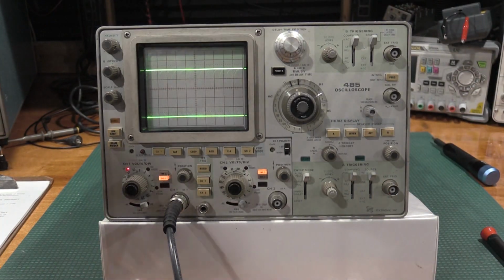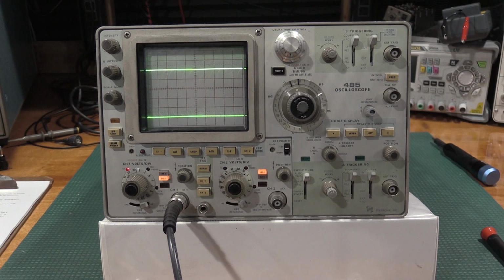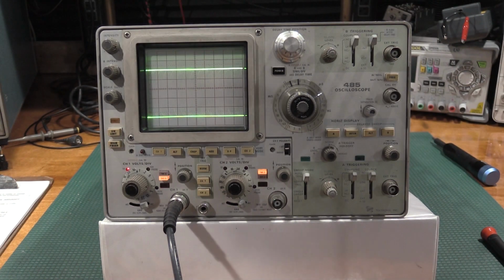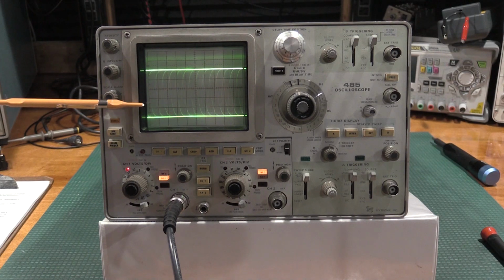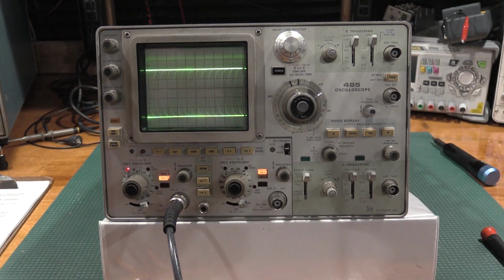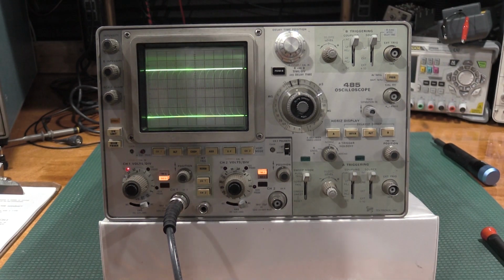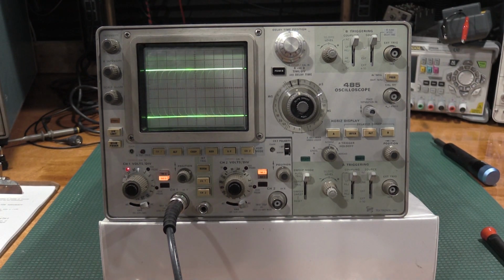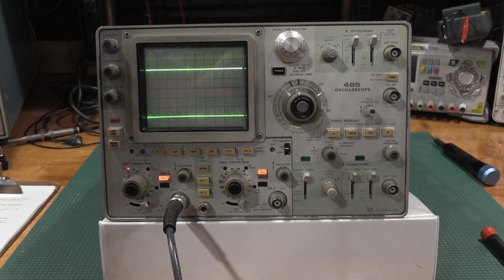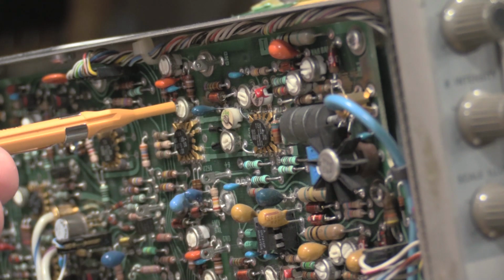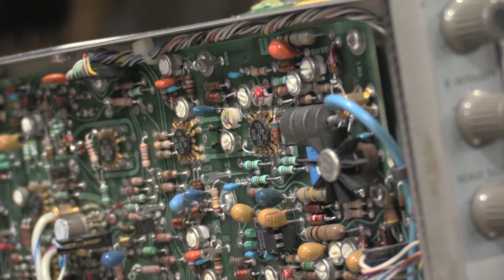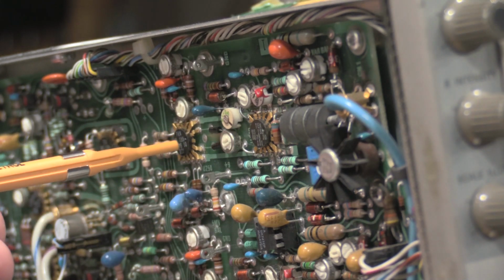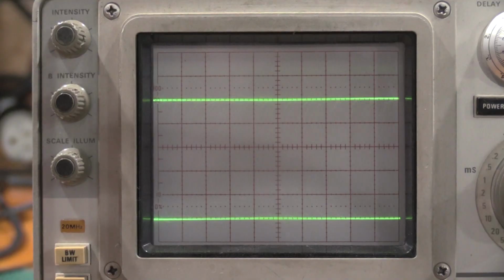Well, it looks like I'm going to need to adjust the trigger a little bit because it's being difficult. I can't trigger on this signal, but it'll be good enough to adjust the vertical. So I need to adjust channel 1's gain for 6 divisions of display with the way I have the PG506 set up. And I'm looking for R255. R255 is going to be right here, and the same place for channel 2 down here right on top of the amplifier IC.